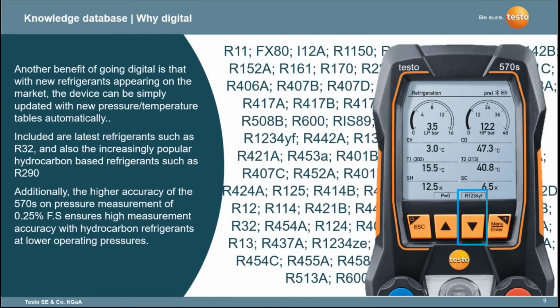One other thing, particularly with the 570s, the higher accuracy of the 570s is particularly relevant where we're working on R290 based systems, where typically the operating pressures in the system will be much lower. So you need that level of accuracy to get a much higher measurement accuracy generally. The other manifolds typically are 0.5% full scale accuracy. The 570s has this slightly higher accuracy of 0.25% of full scale. And so it makes it ideal for working on R290.